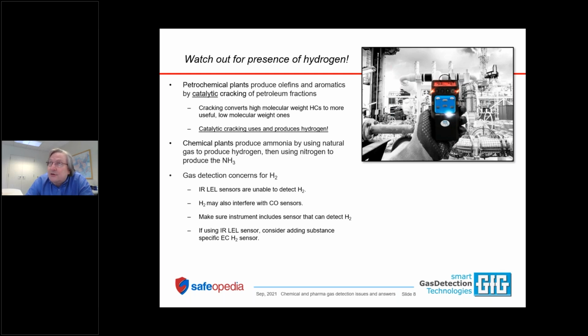Now, a standard carbon monoxide sensor or a dual channel CO/H2S sensor can sometimes have a cross sensitivity to hydrogen of up to 40%. So if you have 100 parts per million of hydrogen around, the CO sensor is going to show a reading of 40 parts per million. So it's responding to hydrogen, not responding to the carbon monoxide.